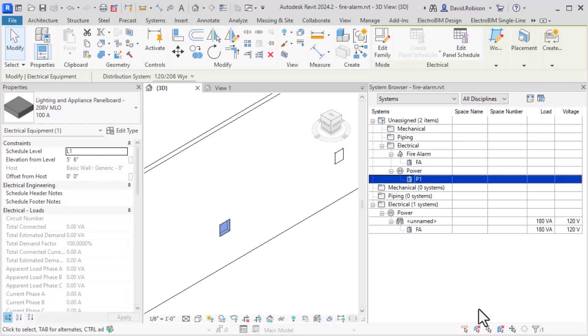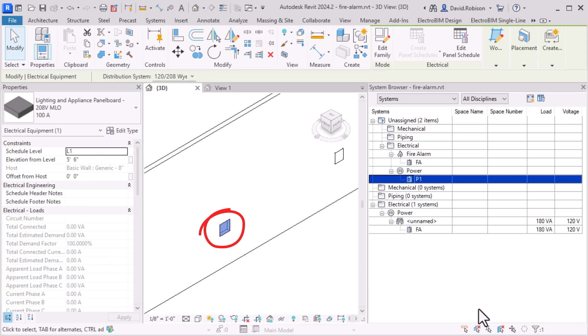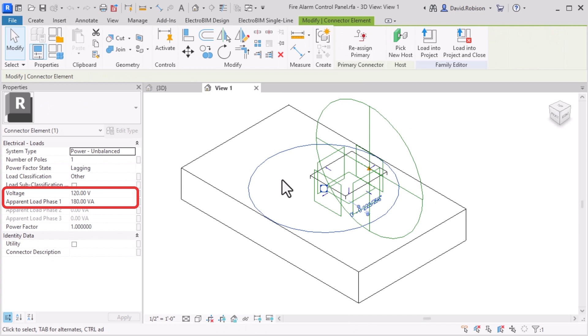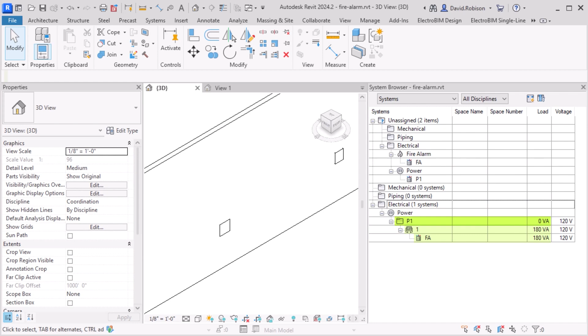To demonstrate that difference, let's take a look at Revit 2024. You can see here I have a power panel, and then a low voltage fire alarm panel. I've added a connector to the fire alarm panel that's a power connector, and put a load on that fire alarm. We can make that connection in Revit 2024, and you'll see the fire alarm panel has a load, the circuit has a load, but the panel it's connected to doesn't actually see that load.